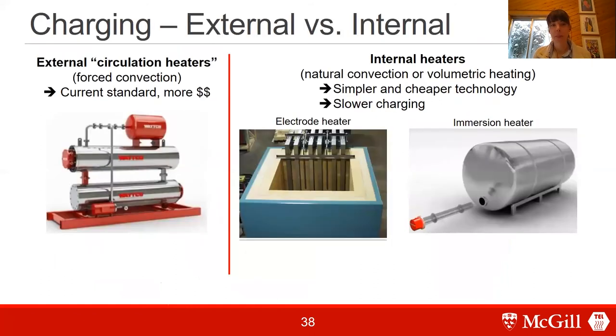We're also looking at different ways to charge the system, meaning heating it up. The off-the-shelf method is a circulation heater, where you extract salt from the tank, heat it externally through a heat exchanger, and pump it back into the storage tank. This is the quickest way of charging your molten salt tank. There are alternatives relying on immersion heaters and electrodes, which are slower and can potentially introduce hot spots if heated too quickly, but they are slightly simpler and might decrease cost if designed to still meet our needs.